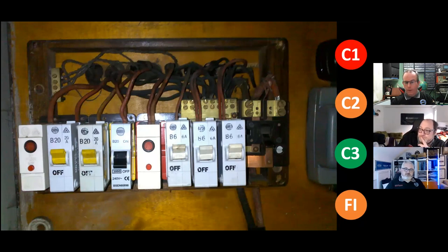I mean, if I was in this, more than likely it is a pensioner's home at the end of the day, because I've been in loads of old people's homes where they've still got lead twin, et cetera. But you are right. I could do a Zs, PFC, PSCC. I can check the earthing, presence of equipotential bonding. What else can I do? I could switch the main switch off. I could maybe put an insulation resistance test across the board to see what insulation resistance values I have, to gauge the condition, to see whether it's worth doing anything else. But as a general rule of thumb, having just dealt with a recent VIR installation that pretty much fell apart, I personally wouldn't touch it, because I don't want to take responsibility for the alteration and addition.